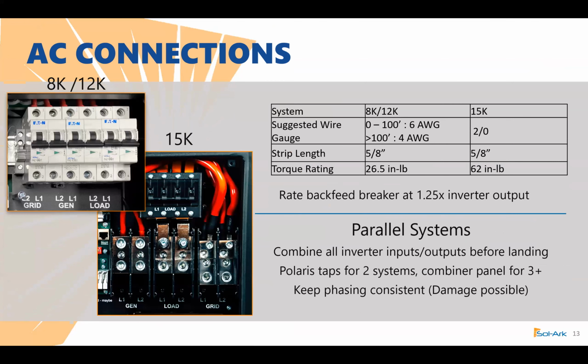And then these are the AC connections I was speaking about before. Your grid connection will typically, with the Sol-Ark 15K, just connect into an AC disconnect. That'll go directly to a meter. If you're using our Sol-Ark 12K, please keep in mind the 125% rule. If you're connecting that connection into a service panel, you want to make sure it's rated for that backfeed breaker of the inverter's output. For the 8 to 12K, the AC connection wire size can be anywhere from 6 to 4 gauge. If you ever go past 100 feet, use 4 gauge wiring. Again, keep that same strip length at 5/8 of an inch. And for the 8 and 12K, do about 26.5 inch-pounds. And then for the 15K, do 62 inch-pounds in torque rating when connecting onto those lugs.